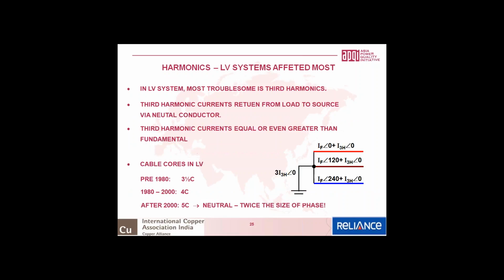This is a very, very crucial point. Now, in LV systems, the most troublesome is the third harmonic. I have shown on the right-hand side a figure where the R phase, Y phase and B phase each have a fundamental component at angle 0, angle 120 and angle 240. The third harmonic component, as you know, is a zero sequence component where the angles are always zero, so they are all in phase in all three phases.